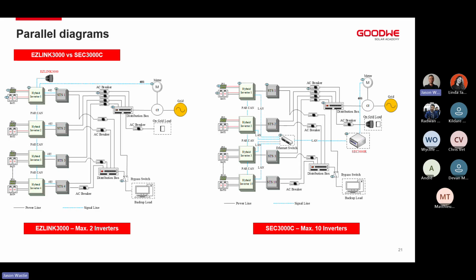Why do we recommend no more than 2? Again, like I mentioned, this is for additional stability, because of the amount of data that needs to transfer, because of the 4 millisecond transfer time that we can ensure, because of unbalanced outputs or unbalanced loads possibly, and that kind of thing. It does make the system a lot more stable if we're doing it through a full-on controller rather than the communication dongle, which does work for 2 units. With 2 units, the communication is a lot quicker. There's only 2 of them, and everything does work as it is expected to.